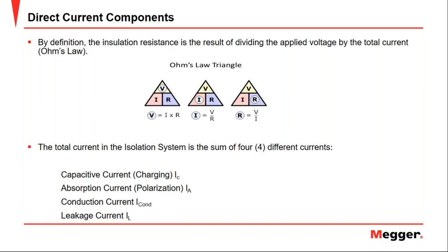Because immediately after we start supplying the motor with a DC voltage, four currents appear in the motor insulation. These four currents are the following: first, capacitive current, or you can name it charging current too. Second, absorption current or polarization current. Third, conduction current. And fourth, leakage current. The total current will be the sum of those four currents. Now, knowing this, let's take a look at the electrical behavior of each one of them.